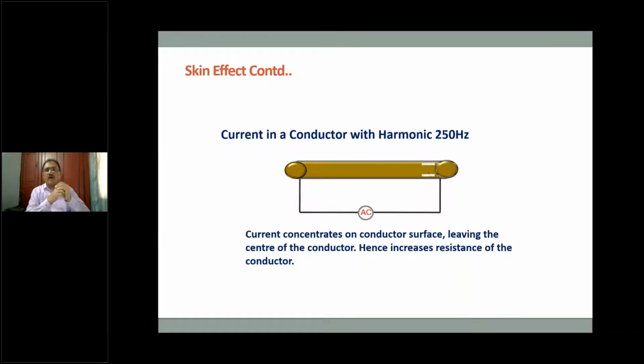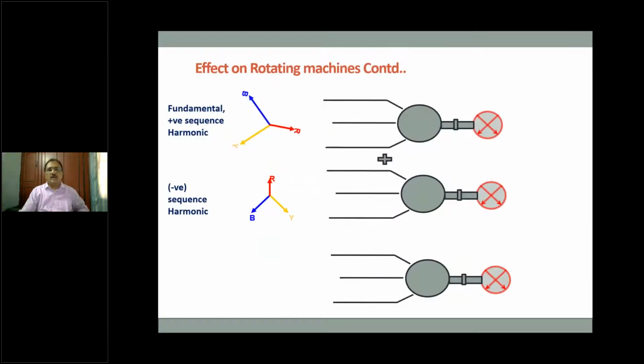Even when you do a walkthrough in the electrical panel room, from the transformer to the main panel, if the bus duct has been used, and if there is harmonic in the network going towards the grid, you will find humming and heating, telltale signs in the panels. Now, like I told you, the humming and the heat are one way by which you will know the presence of harmonics.